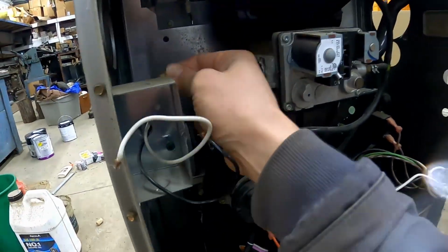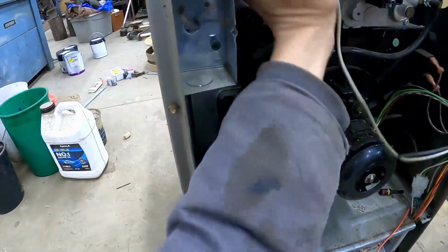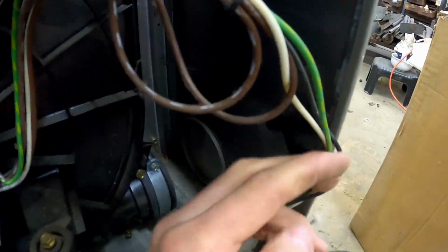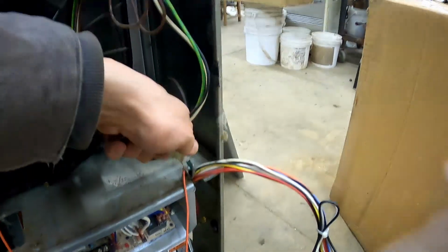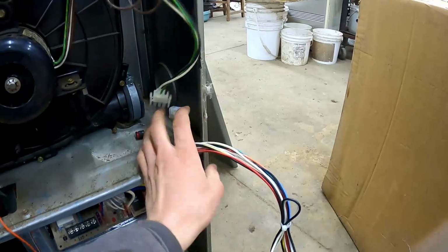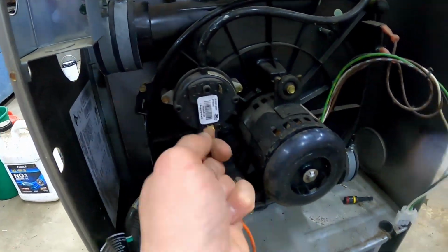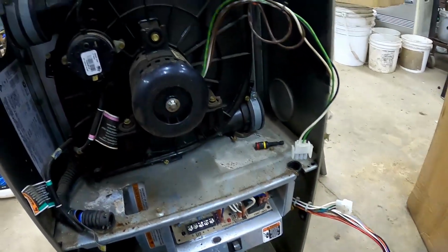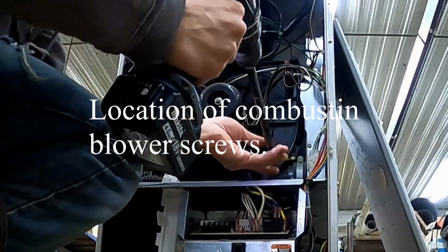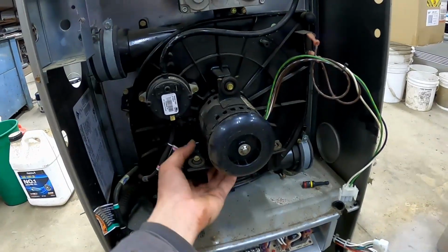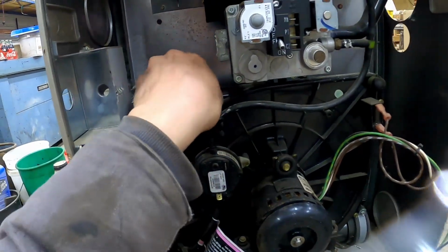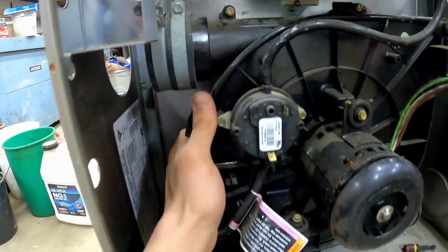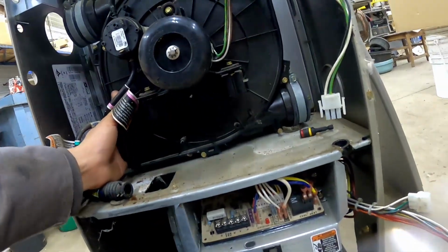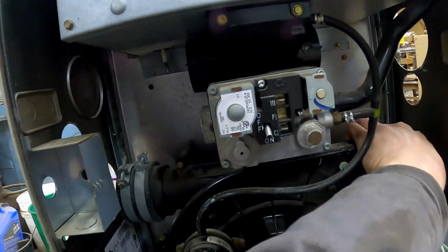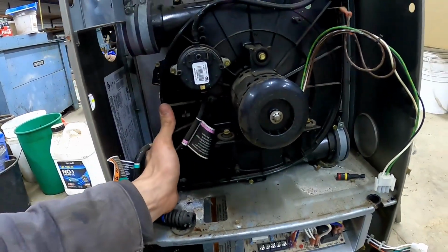And then our power coming in. There's just a clip here on the side of the furnace. Unplug our combustion blower. Other side of our pressure switch. That's the wiring harness down out of the way. Since we loosened these 4 screws that held our combustion blower in place, we can work this off gently. It's not uncommon for them to be kind of stiff though, coming off.